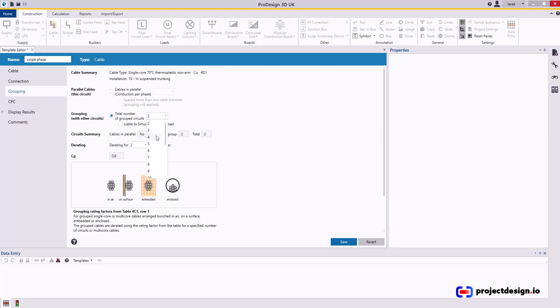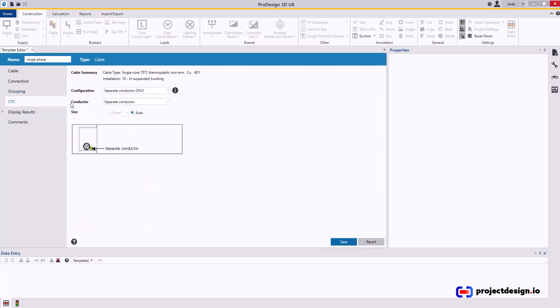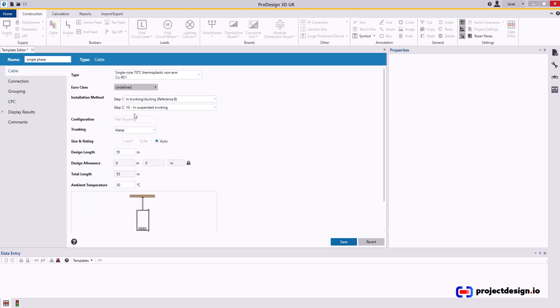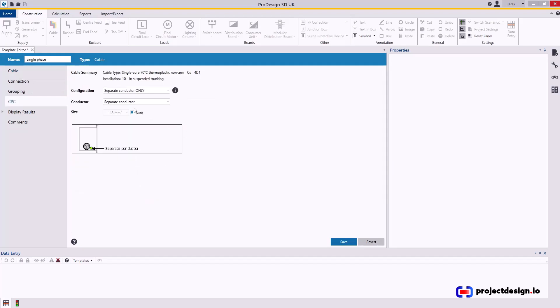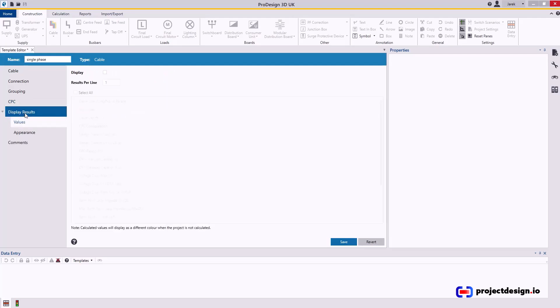CPC, that will be separate conductor. And again, same as in here, I'm going to ask you to keep the size on auto, because this will be applicable to lighting and power circuits. So I'm leaving it as auto, and CPC will be also auto, separate conductor only. So not calculating trunking and separate conductor. Display results, I'm not going to display results, and that's it.